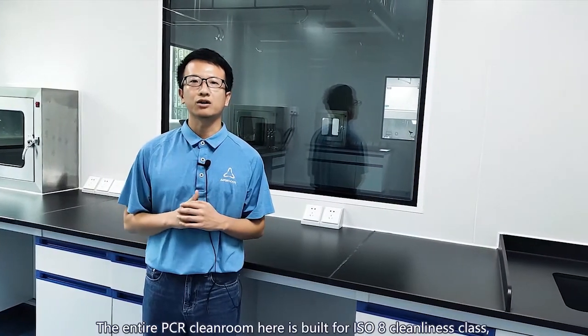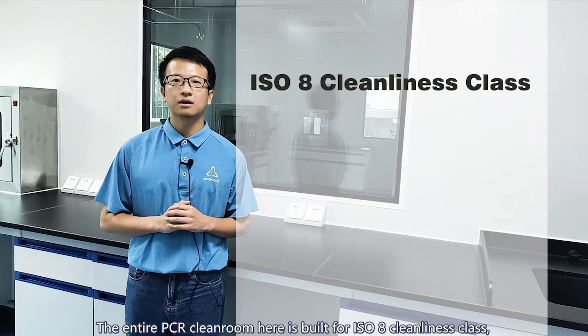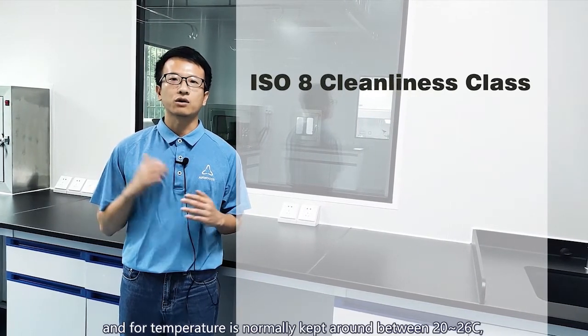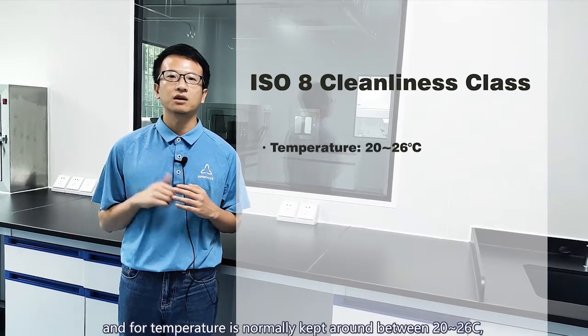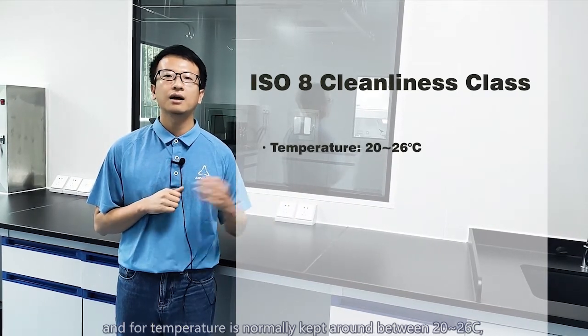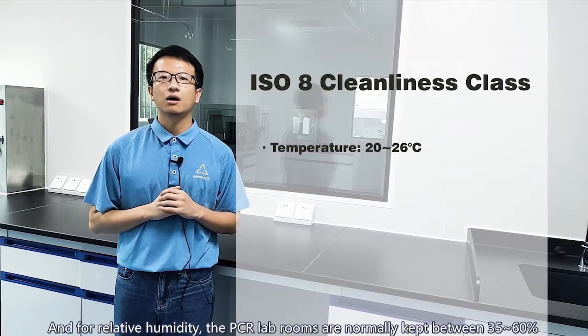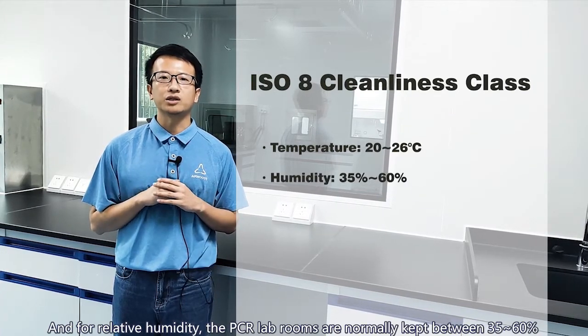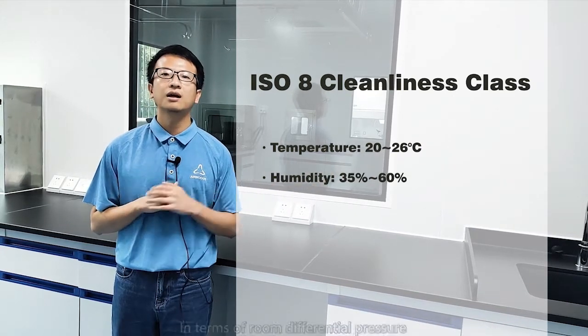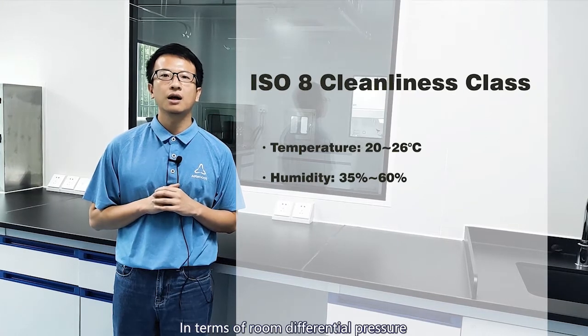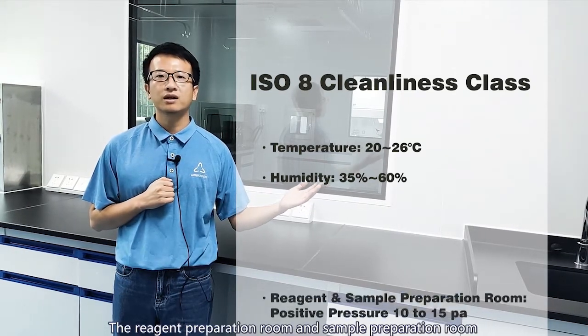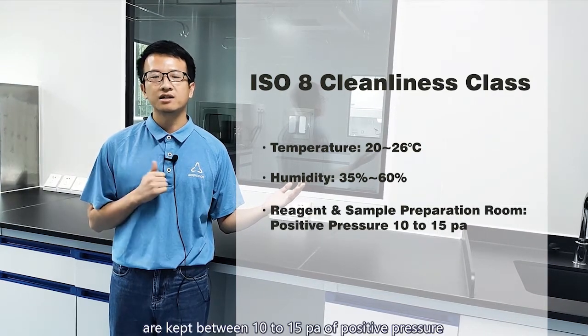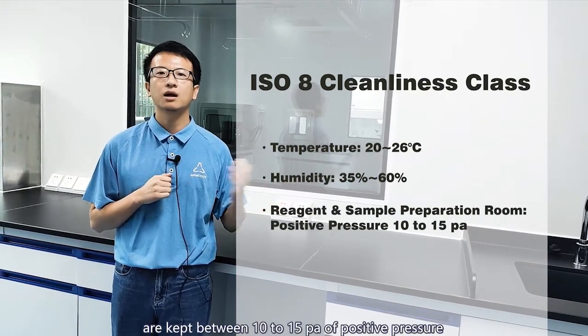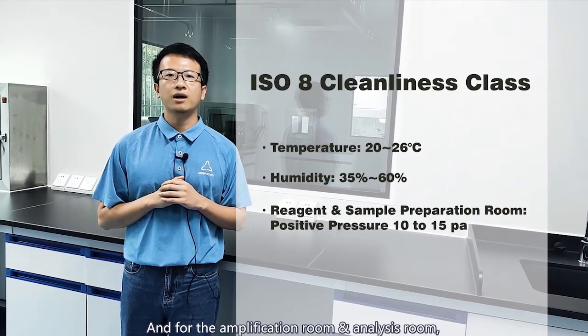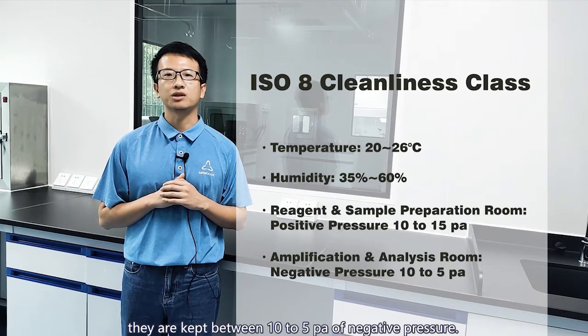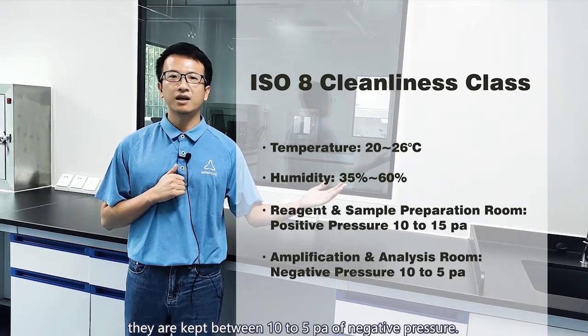The entire PCR cleanroom here is built for ISO 8 cleanliness class, and for temperature, all the rooms are normally kept between 20 to 26 centigrade, and for relative humidity, the PCR lab rooms are normally kept between 35% to 60%. In terms of the room differential pressure, the reagent preparation room and sample preparation room are kept between 10 to 15 Pa of positive pressure. And the amplification room and analysis room are kept between 10 to 5 Pa of negative pressure.